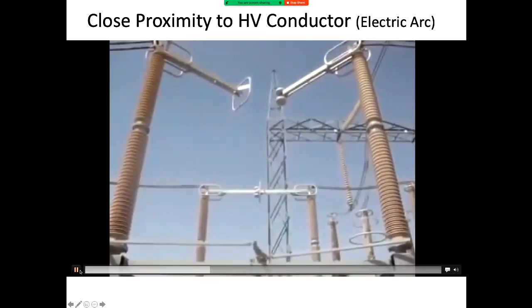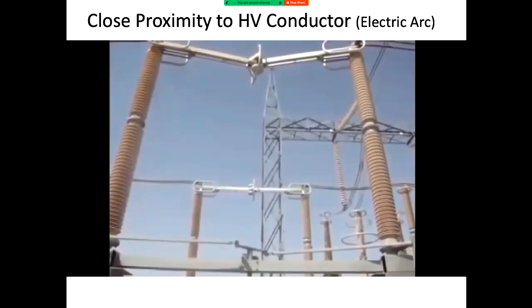This is about proximity to an HV conductor. A good little video shows that you don't actually have to touch a high voltage conductor to get a zap. The high voltage can cause the insulation, which is air, to break down if the field strength is high enough. Dry air is normally an insulator, but it has about 30 kV per centimetre before it breaks down. So if a person connected to earth reaches out and isn't touching it, but is close, they can get zapped. It's not just touching it, it's being in proximity to it.